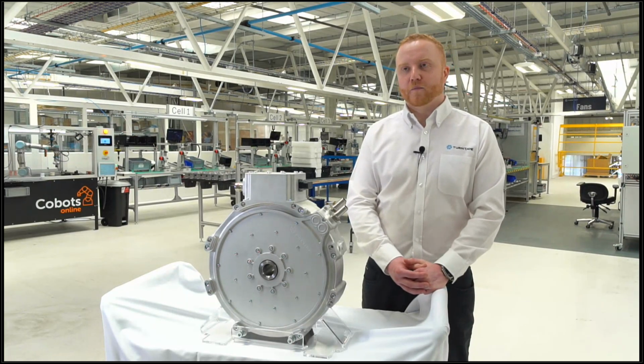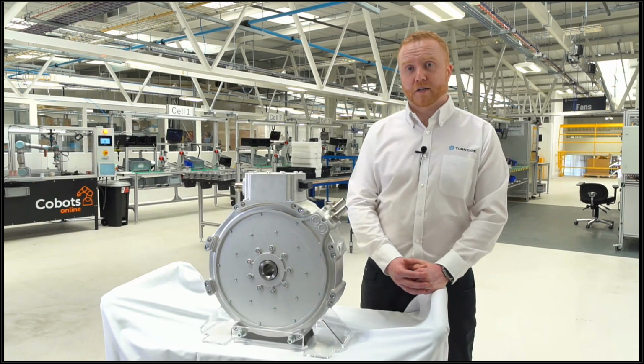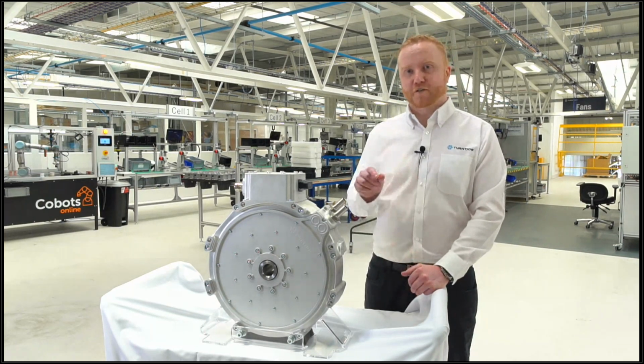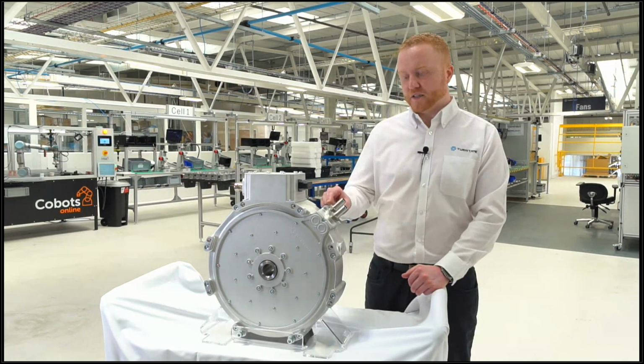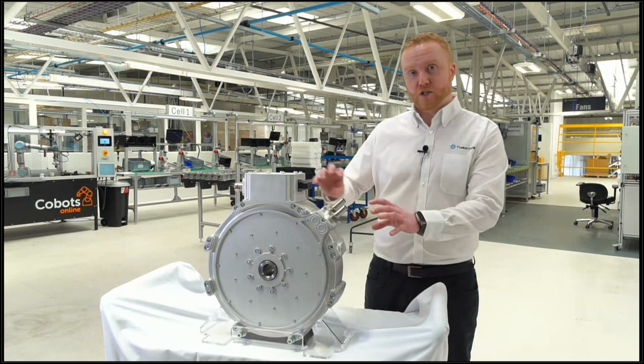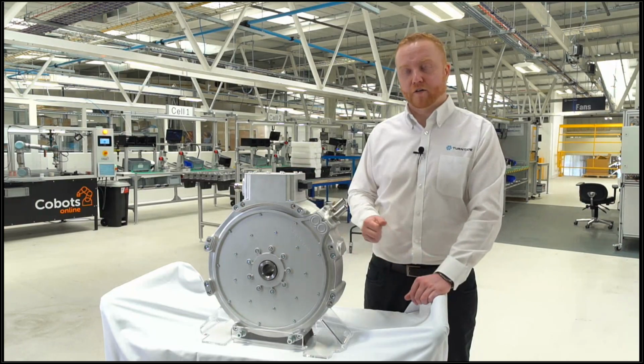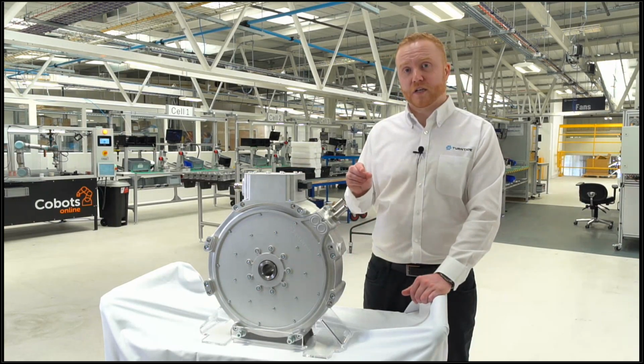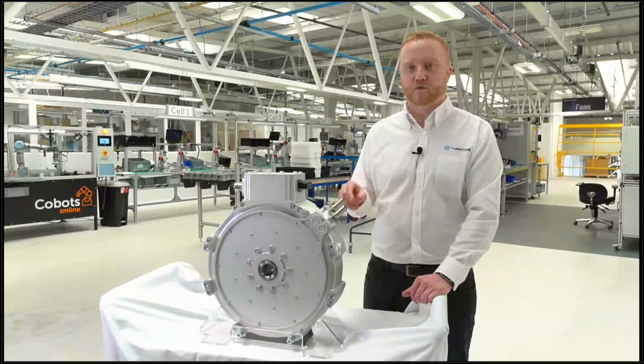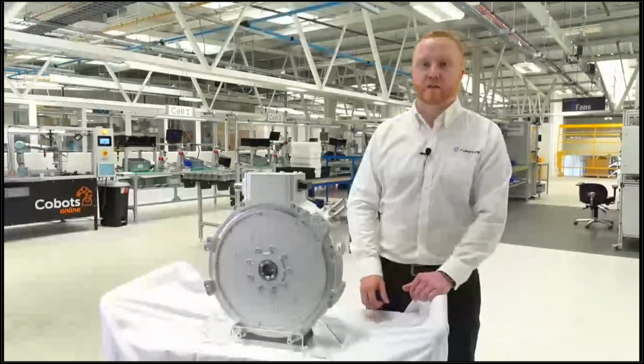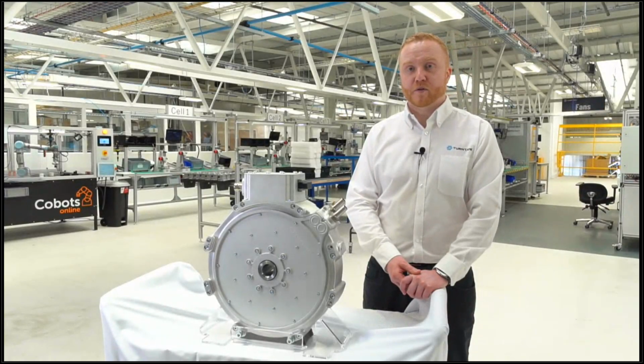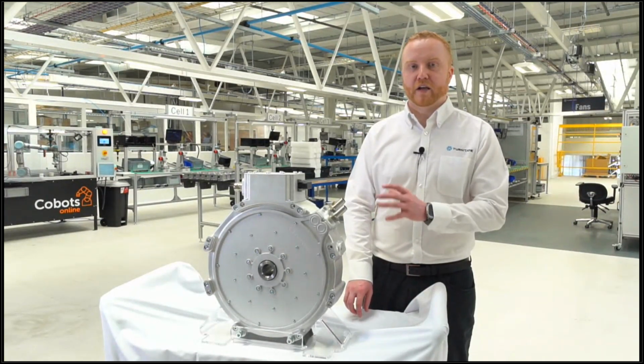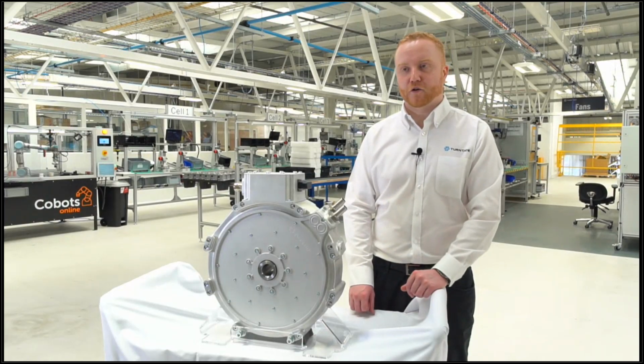I guess potentially. In the design, we've attempted to maximize the minimum aperture within the cooling profile. We picked a slightly larger threaded hole for the inlet and outlet, and through the coolant rail and the channel around the surface of the stator, we've tried to maximize the aperture size to avoid small bottlenecks that could fill with debris. From a system perspective, we always recommend a filtering system to protect the cooling system generally, not just the motor but also things like inverters, which tend to be more sensitive. Within our design, we've tried to make it as robust and rugged as possible, because not all systems are perfect and inevitably there will be debris in the system.